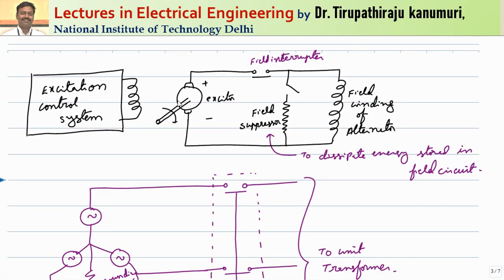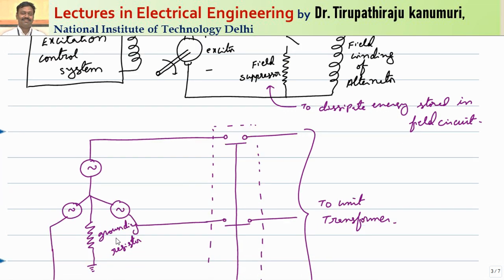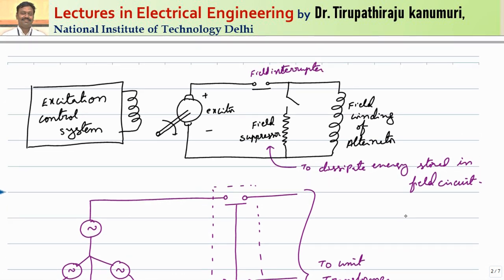Let us see the field system in detail. It will have the exciter control system supplying the field to the exciter, and the exciter will produce the EMF that supplies the field to the alternator. The alternator stator is connected in star and grounded through a resistor, which is used for controlling or decreasing the effect of ground faults in the stator. This is then connected through a circuit breaker to the unit transformer and then to the grid. Whenever a fault happens, along with the alternator circuit breakers, the field of the alternator must also be removed.